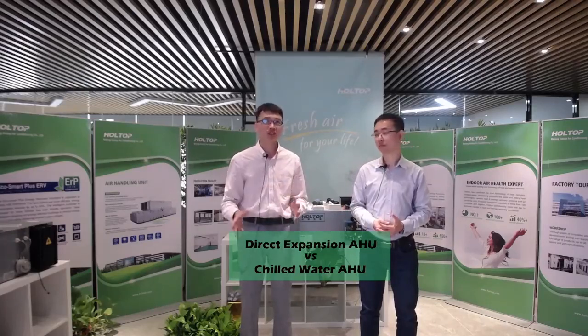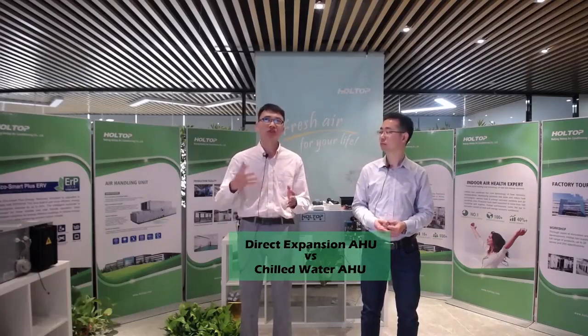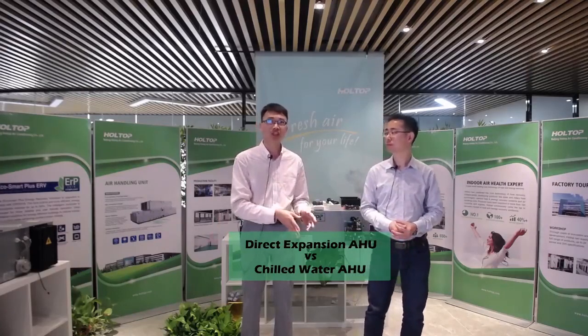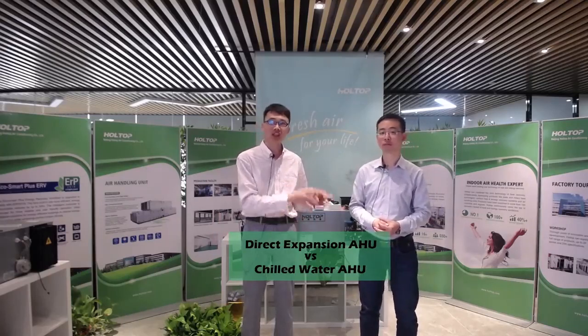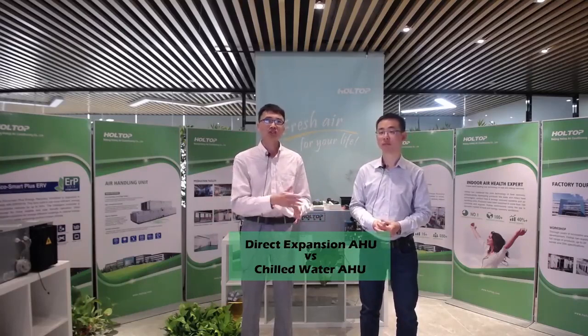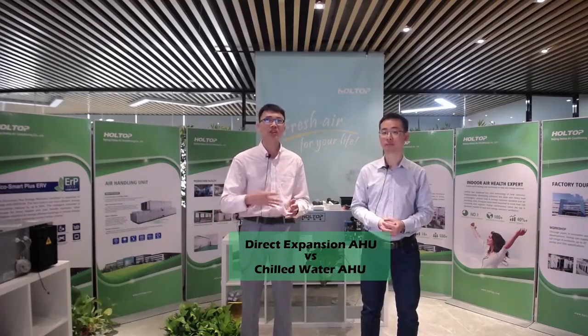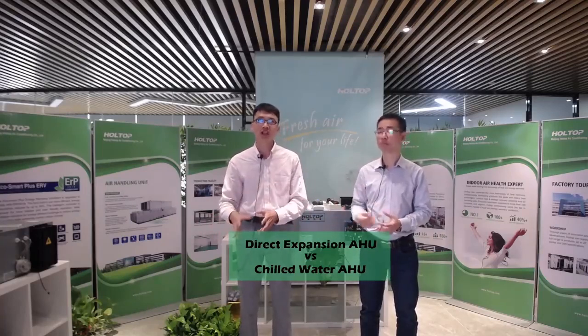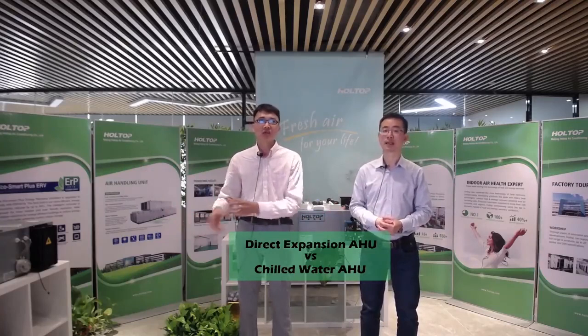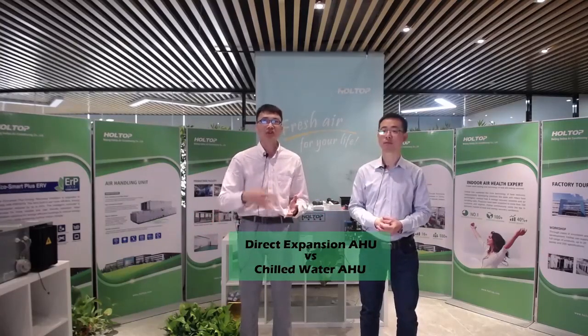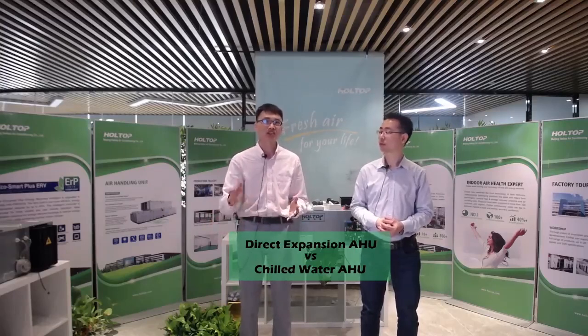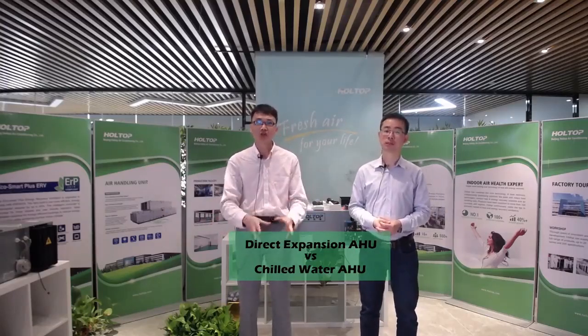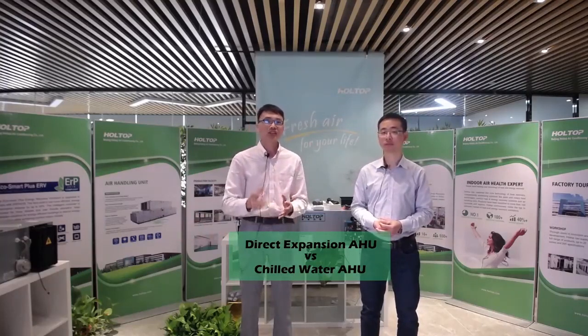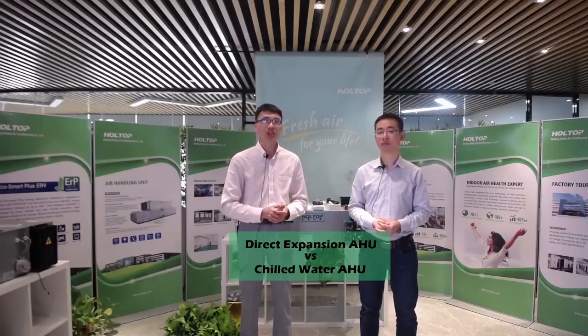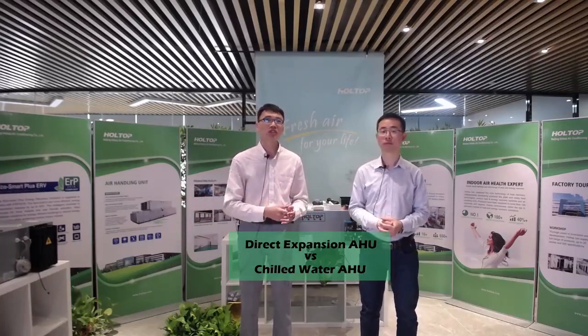But in the chilled water system, the cooling effect from the refrigerant is first transferred to the chilled water, which is then used to cool the air inside the AHU. There is more energy loss of the cooling effect when it is transferred from the refrigerant to the chilled water and then from the chilled water to the air. Due to this reason, the chilled water system has less cooling efficiency. That is, refrigerant to chilled water, then chilled water to air. The chilled water acts as the secondary cooling medium in this system. In a word, a longer energy transferring process means more energy lost and less energy efficiency.